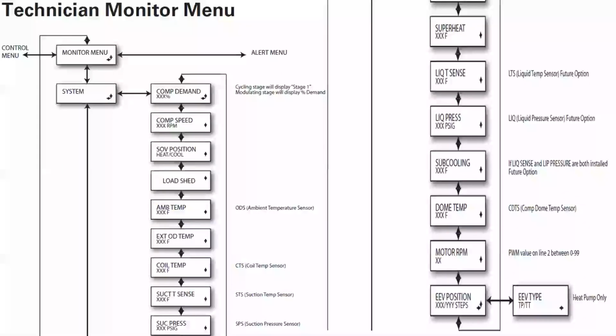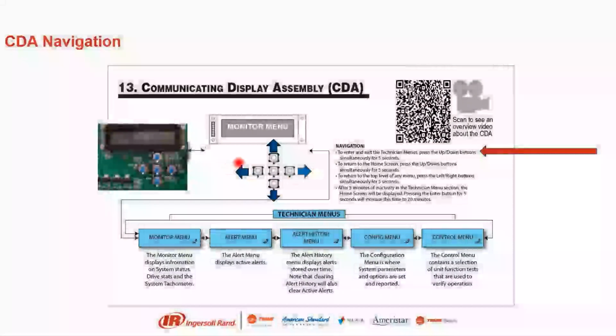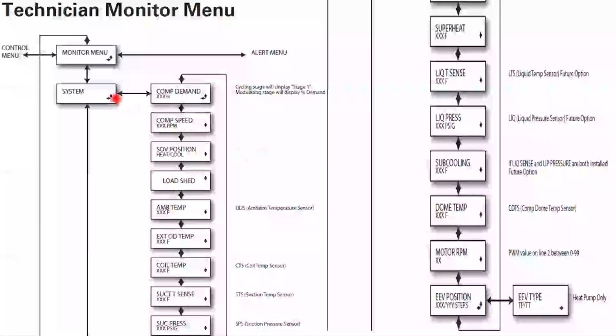From monitor menu, again, we're pressing and holding the top and bottom button, and then it's going to display monitor. So now we're in monitor. We're going to scroll one down to system, and then we're going to scroll right. And now we're just going to be peering into the system sensors. From this, we're going to see compressor demand. In check charge heating and check charge cooling, this will show 0, just so you know. But if we're in normal operation, we're going to be able to see what the actual compressor demand is. We can see our compressor speed. We can see if the switchover valve or reversing valve is in heat or cool.